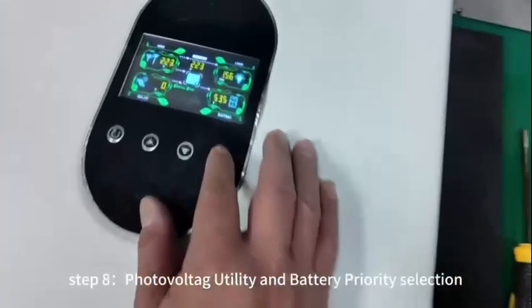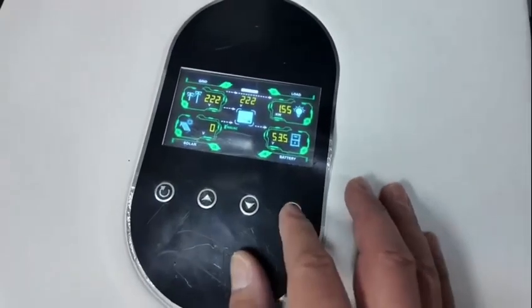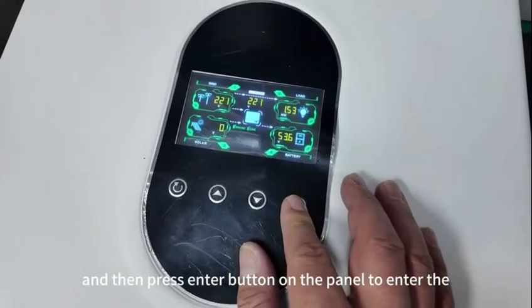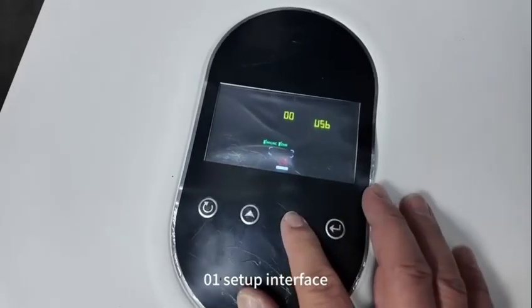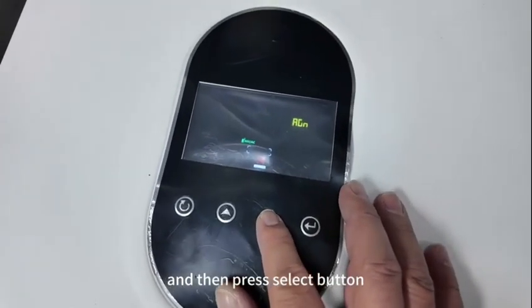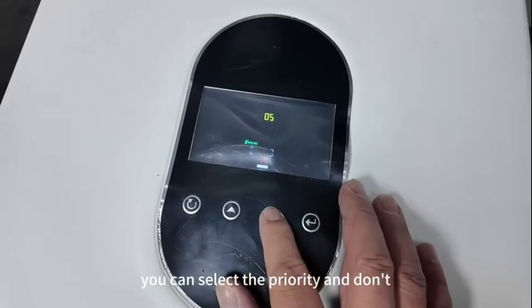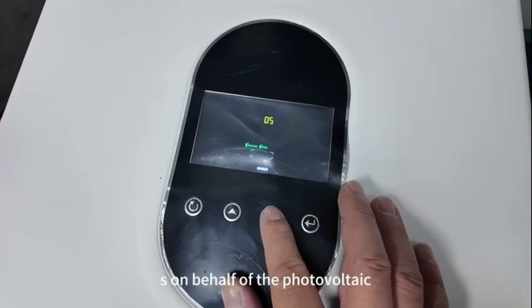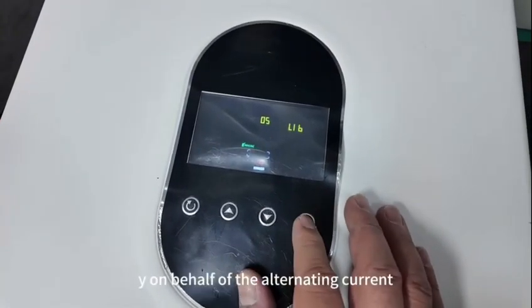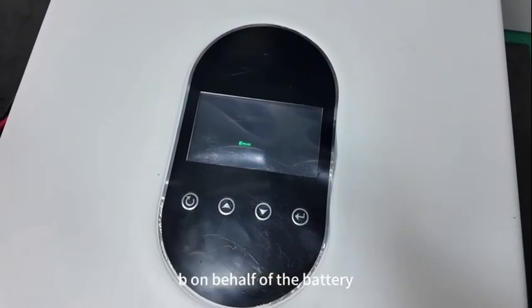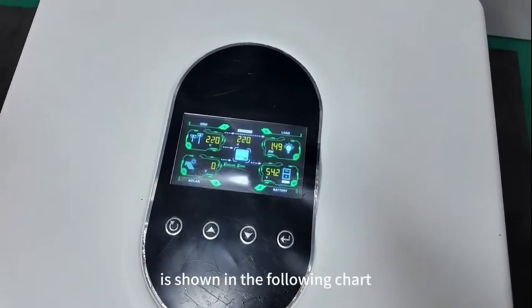Step 8. Photovoltaic, utility, and battery priority selection, and then press Enter button on the panel to enter the 0-1 setup interface, and then press Select button. You can select the priority, S on behalf of the photovoltaic, U on behalf of the alternating current, B on behalf of the battery, as shown in the following chart.